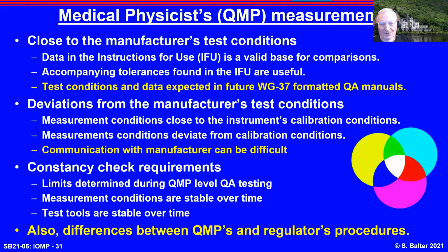You look at two issues. Are the measurement conditions close to your instrument calibration conditions? And I will give a hint in terms of radiation output. Most diagnostic dosimeters are tested with relatively soft X-ray beams. Many modern beams are very highly filtered, so one has to look at the energy dependence and the energy compensation to decide if your measurements are very different than the calibration lab. Again, understand the calibration lab so you understand what you're seeing in front of you. Because of all these permutations, one gets into endless discussions.